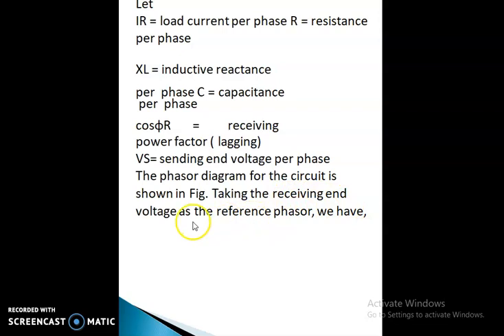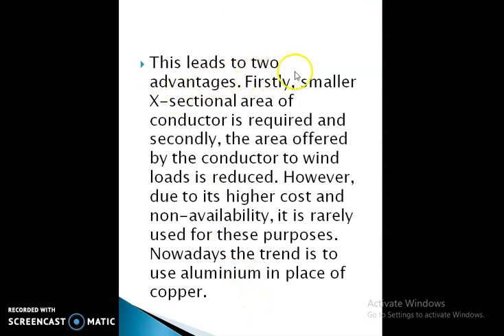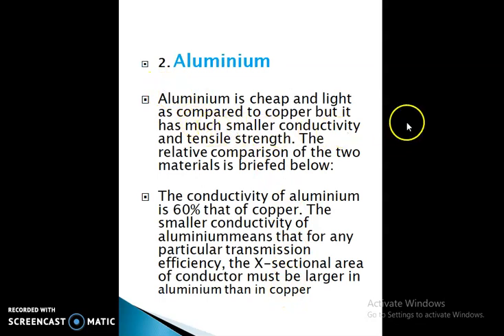The types of conductors: First is copper. Copper is an ideal material for overhead lines owing to its high electrical conductivity and greater tensile strength. Copper has a high current density, meaning the current-carrying capacity per unit cross-sectional area is quite large. This leads to two advantages: firstly, a smaller cross-sectional area of conductor is required, and secondly, the area offered by the conductor to wind loads is reduced. However, due to its higher cost and non-availability, it is rarely used nowadays.